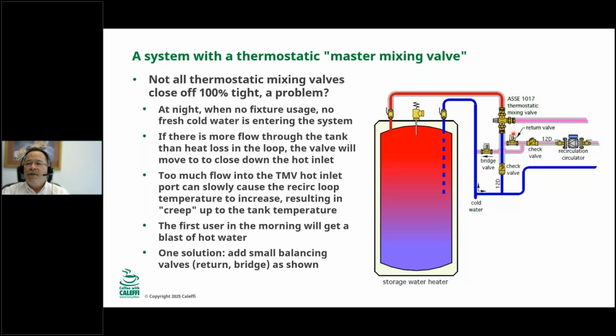You close it almost all the way closed so that it allows very little water into the tank, just enough BTUs coming out of the tank to equal, ideally, the heat loss in the piping to atmosphere out here. So if you can get that balanced just right, then you won't get temperature creep. But this valve is just barely cracked open, and that takes a little bit of work, a little bit of practice, but it can be done.